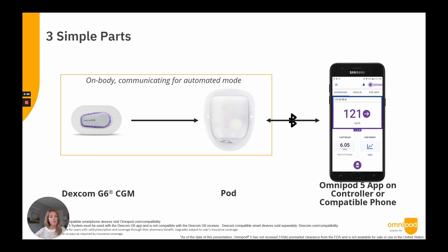Automated insulin delivery is possible when the Dexcom G6 CGM and pod are on body and communicating. The Omnipod 5 app is not required to be nearby for automated mode, but is used to view data and notifications, send insulin delivery commands, or activate and deactivate pods. A new feature will be a SIM card built into the controller, free for the user, that will automatically allow data transmission to the cloud in real time. The Dexcom G6 CGM will be sold separately, and Omnipod 5 will only be compatible with the G6 app on a smartphone, not the G6 receiver.